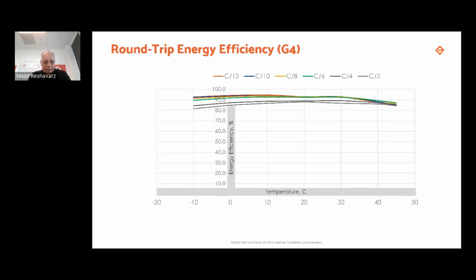Extensive studies on the C rate suited for stationary applications, C over 12 hours duration all the way to 2 hours at different temperatures. What I'm showing here is from minus 10 degrees C to 45 degrees C at six different C rates. As you can see, under most conditions, the energy efficiency, round trip efficiency, is more than 90%, especially long duration ones. C over 2, C over 4 drops a little bit, but nevertheless, very good performance for this type of batteries.